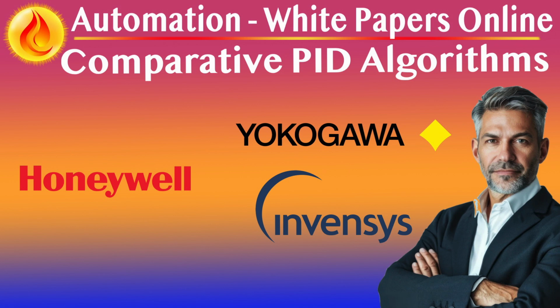Real-world implications. For greenfield projects demanding modular customization, adaptive control, and multi-loop synchronization, e.g. batch pharma, chemicals, food, Yokogawa offers a more flexible platform. For brownfield migrations, where minimizing loop disruption is critical, especially when migrating legacy pneumatic electronic control, Invensys with series algorithms can maintain loop continuity while gradually upgrading capability.